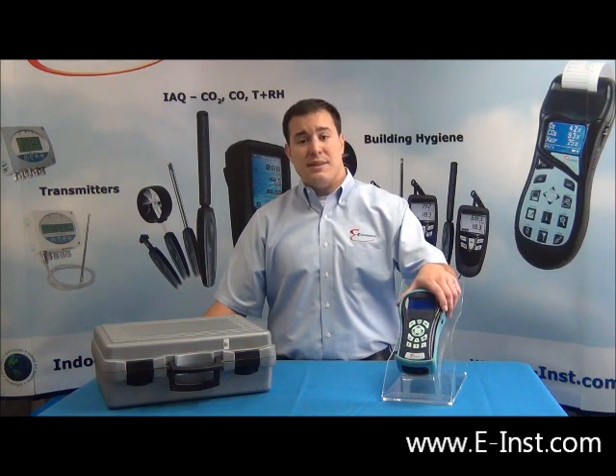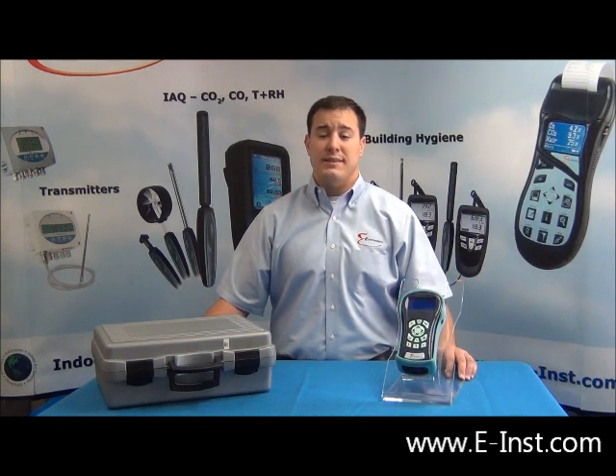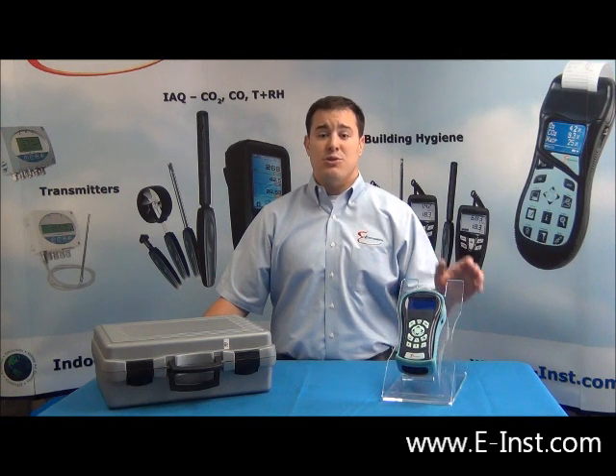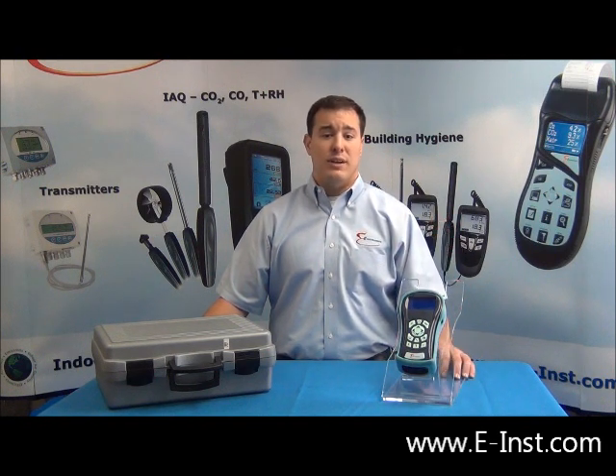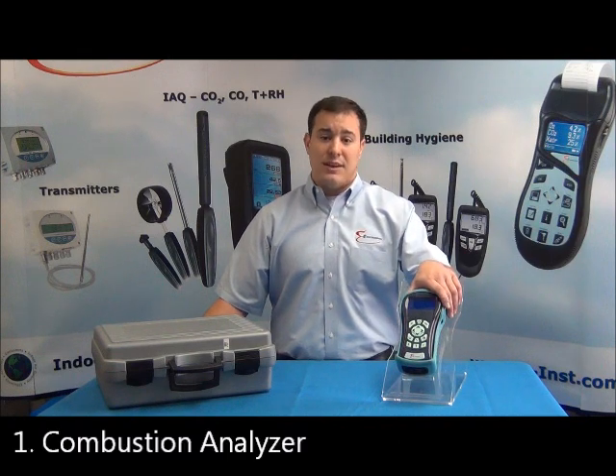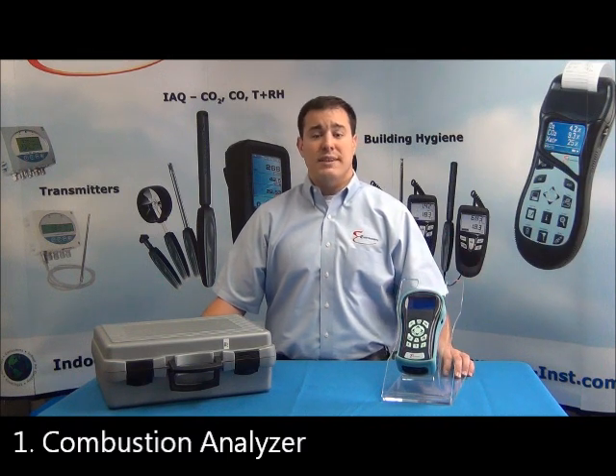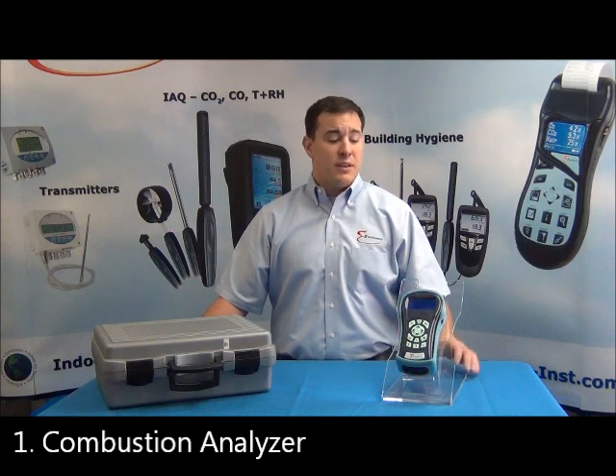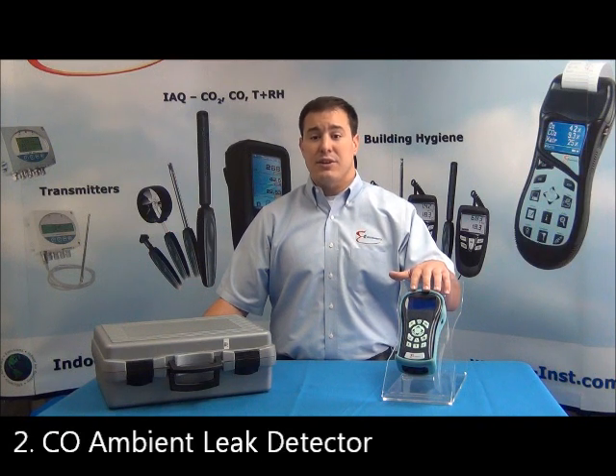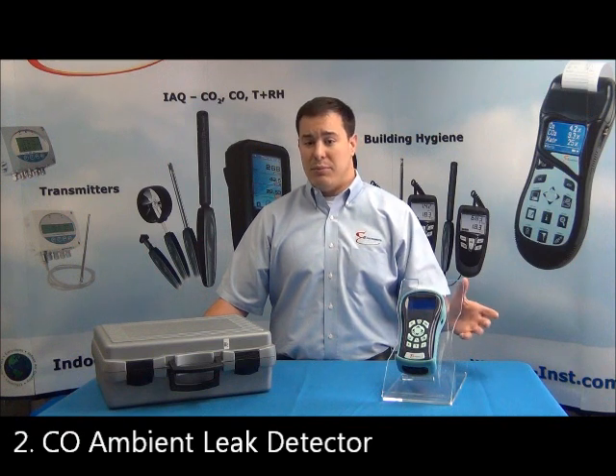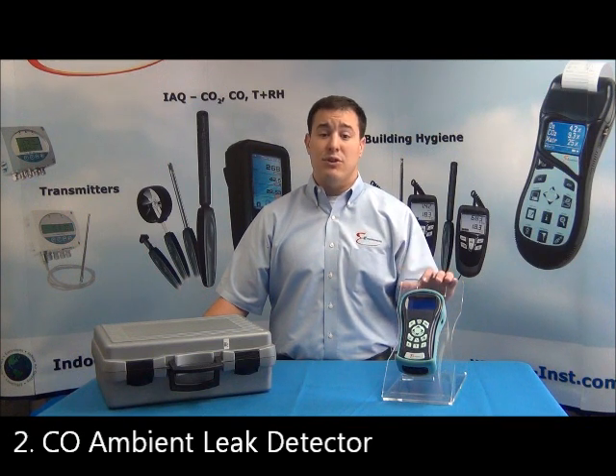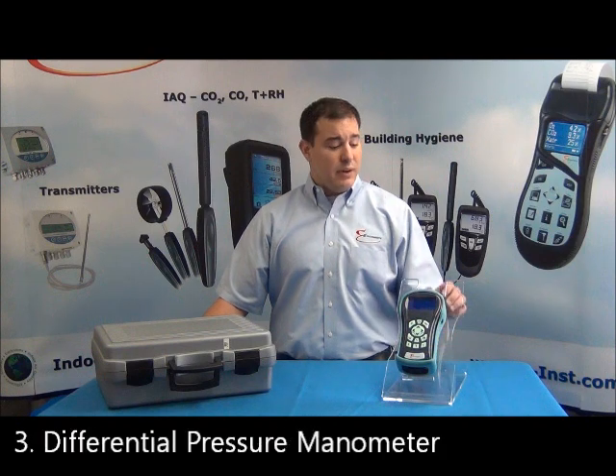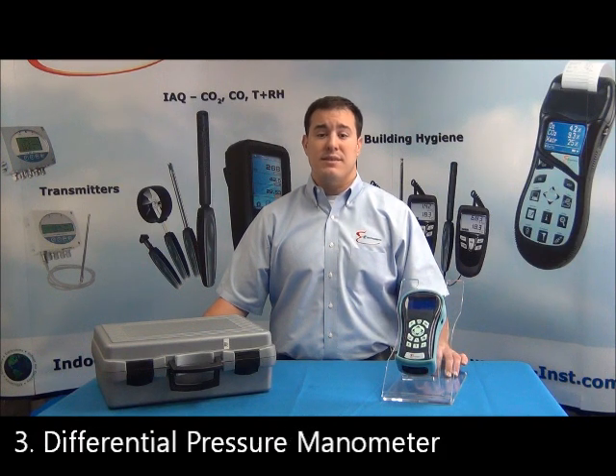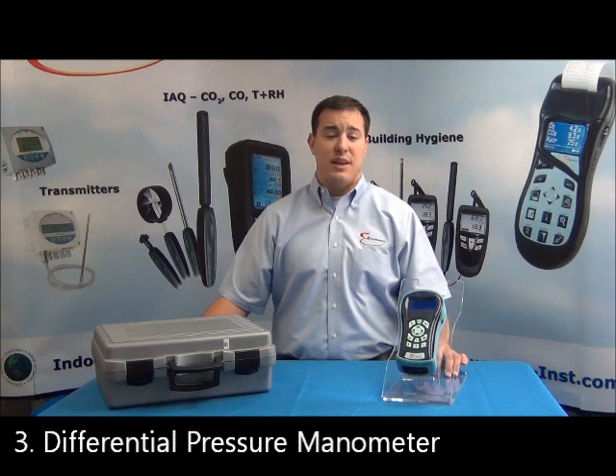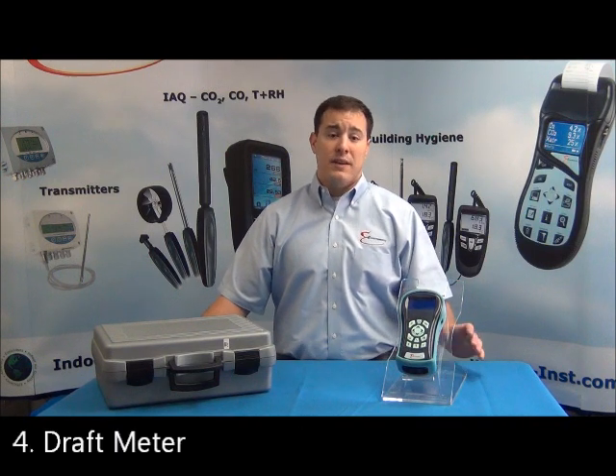Our BTU900 is the perfect analyzer for residential HVAC and light commercial applications, since you have five actual instruments built into the unit itself. Number one, your combustion analyzer for O2, CO2, CO, temperatures, efficiency, and excess air. Two, your ambient CO leak detector, built in for not only the boiler and the appliance safety testing, but more importantly, the safety of you and the building occupants. Three, your differential pressure manometer for gas appliance installs, testing, filter testing, switch testing, static duct pressure, and any other pressure testing. Number four, it's your draft meter.